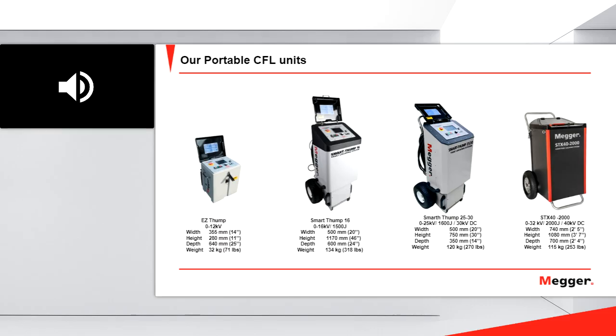But if you have, let's say, lengths of 3 or 5 kilometers, then you can use the Smart Thump 16. And if you have 25 or 30 kV cables, the equipment or the recommendation will be the Smart Thump 25-30. This is for cables with lengths between 3 and 4 kilometers.